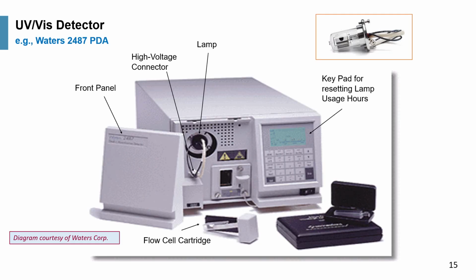I'm going to go through the procedure to replace a deuterium lamp of a UV detector. And the system in this case study is the Waters 2487 PDA, which is very common. And here is the replacement lamp, which costs in excess of $1,000, right? So it should be replaced annually.